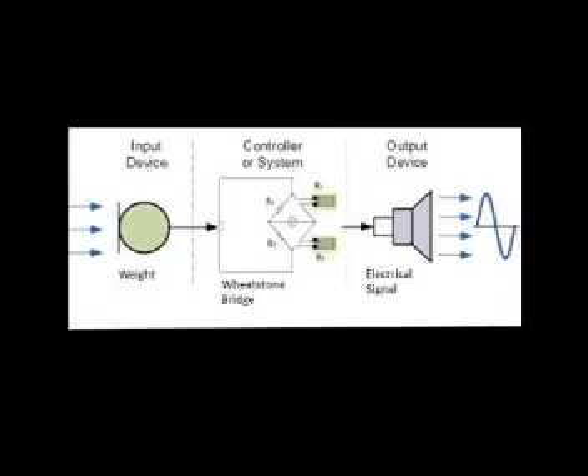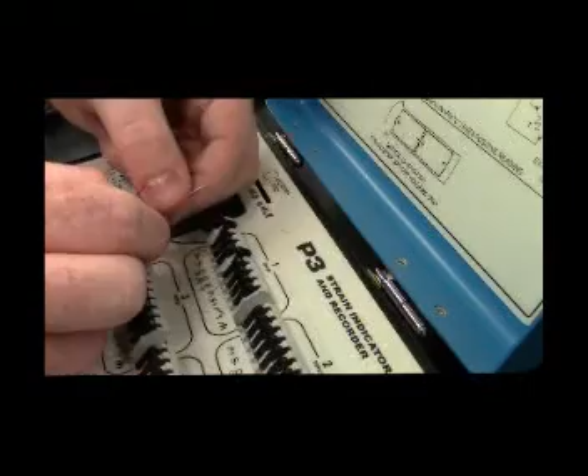As previously mentioned, we already have our strain gauges set up. So we take our cantilever beam and we securely clamp it to the edge of the table. So we now need to connect the wires to the strain recorder. The black wire is going to go into the positive P terminal. The white wire for the signal is going to go into the negative S terminal. And the red wire is going to go into the negative P terminal.